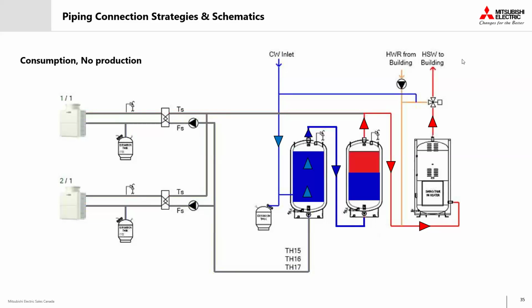They charged the tanks. As our stored water is drawn down, the tank sensors throughout this circuit are monitoring that depletion of our hot water. Once the storage drops to a pre-programmed threshold, our controls will activate the heat pumps to recharge those tanks once again. This is one of the reasons we usually like to highlight why proper sensor placement and control strategies are so important for that reliability and consistent hot water supply out into the building.